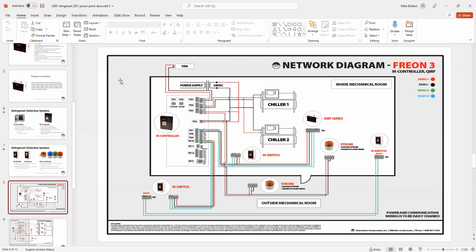Does this diagram, the horns and the strobes, are they universal? Can they be used by any digital output? The horns and strobes require 24 VAC or VDC to power. Yeah, they're pretty much universal. Any relay will turn them on or off.